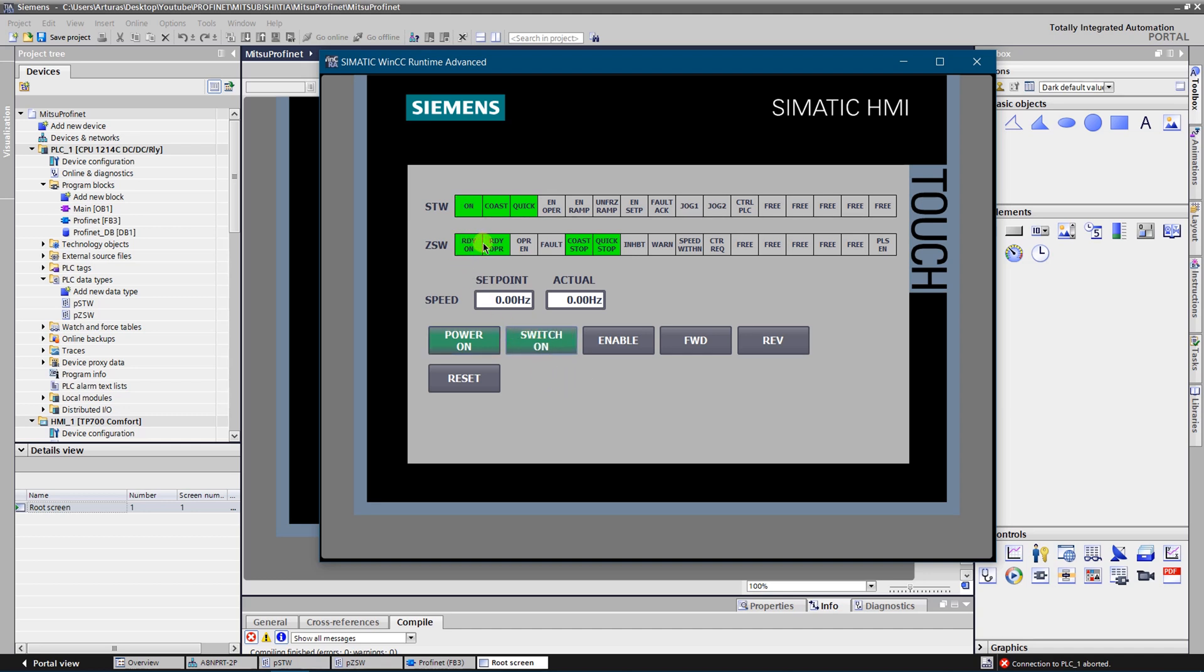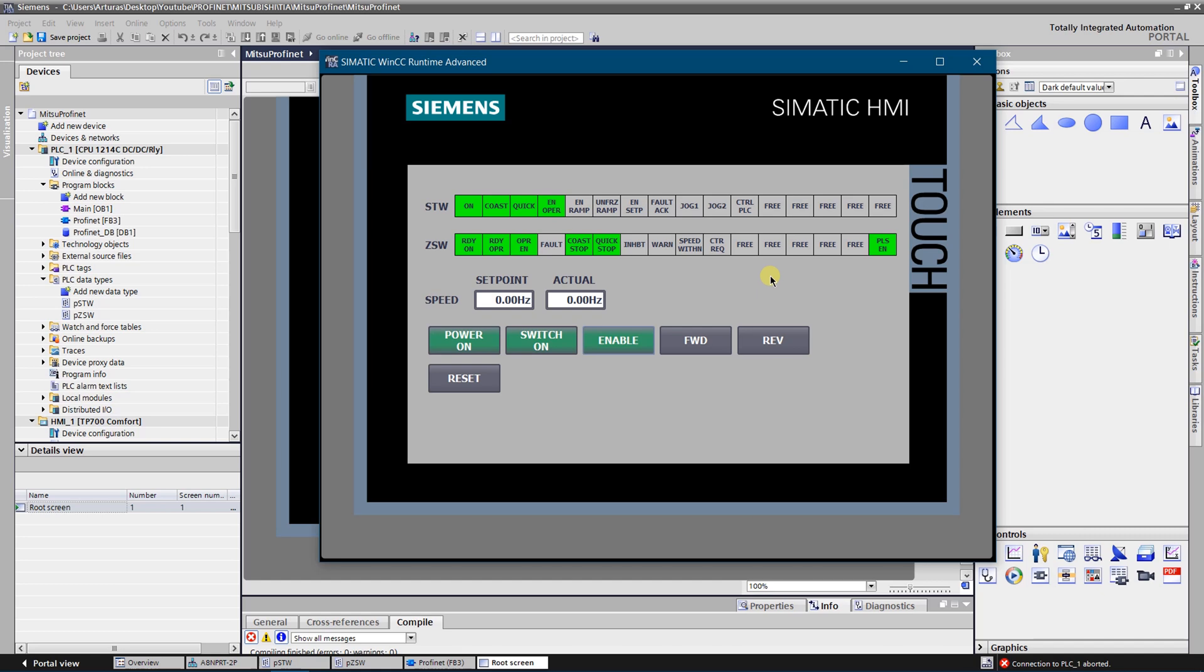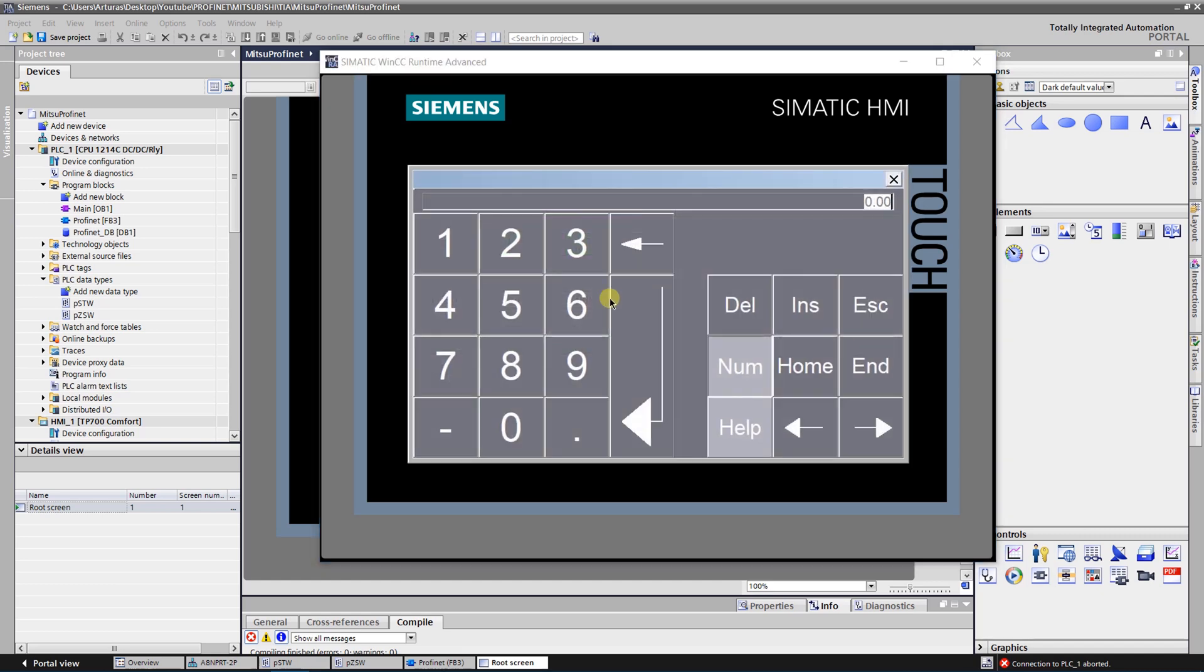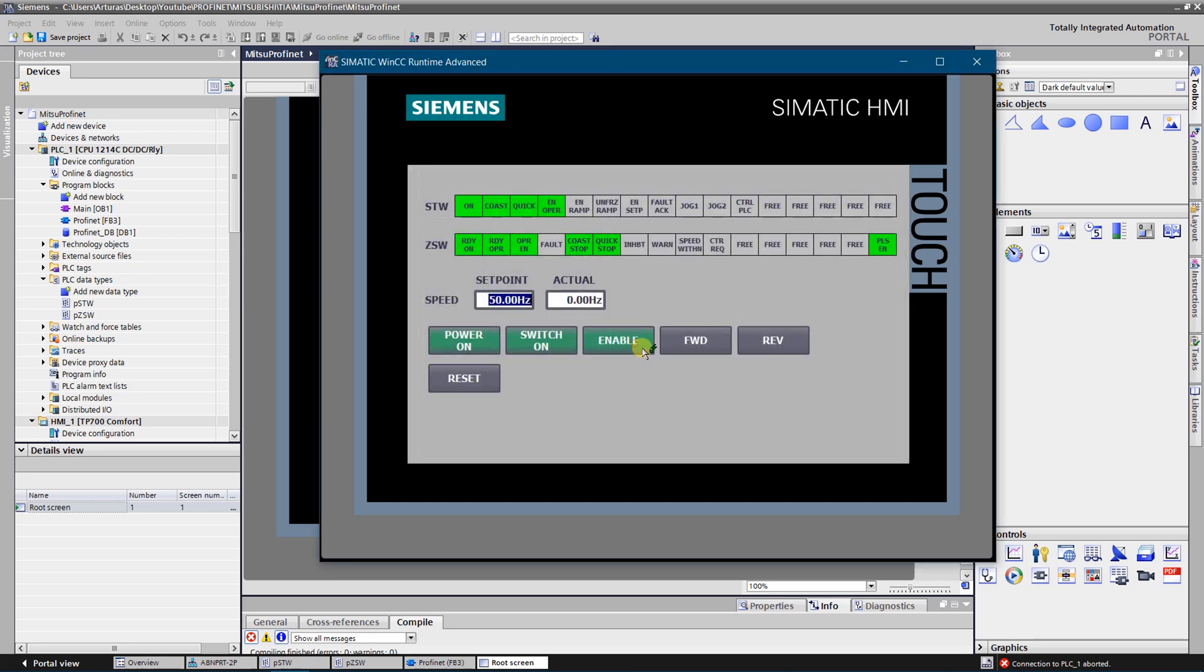Now I've got the answer that it is ready to operate. Now let's try to enable the operation. So operation is enabled, pulses is enabled as well, and VFD is waiting for commands to rotate forward and reverse. Let's give a 50 Hertz setpoint and try to rotate forward. As you can see it's rotating forward at 50 Hertz. Now let's stop it.